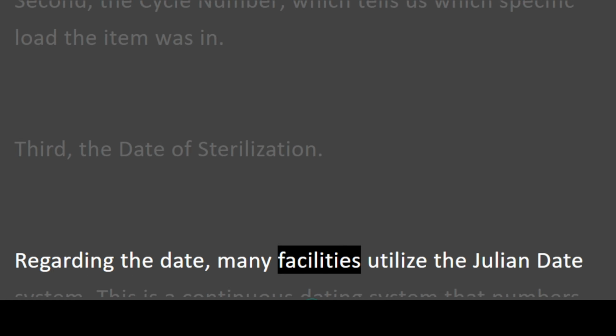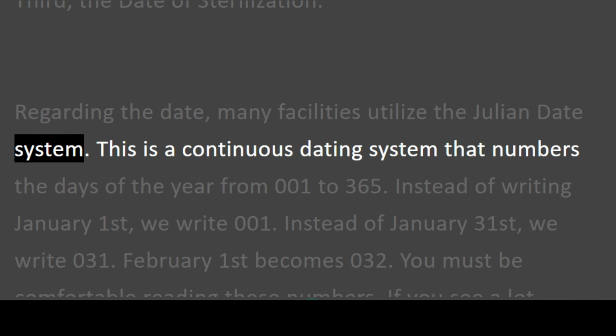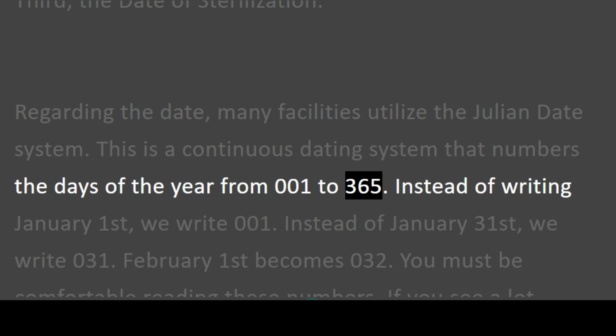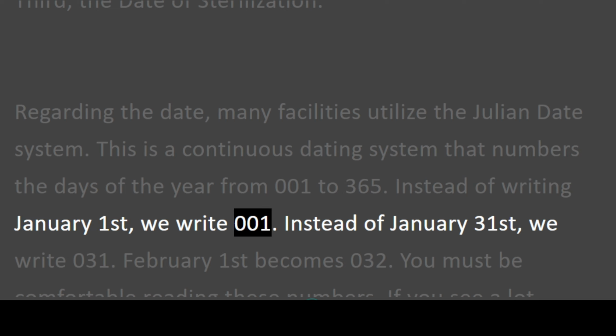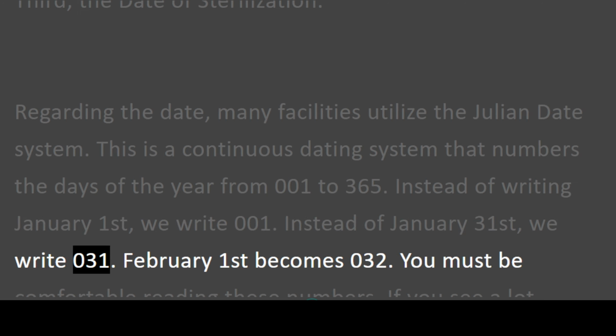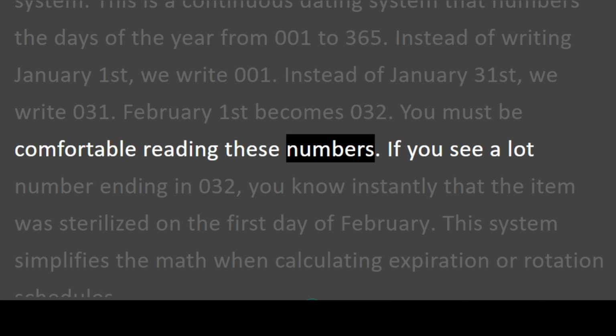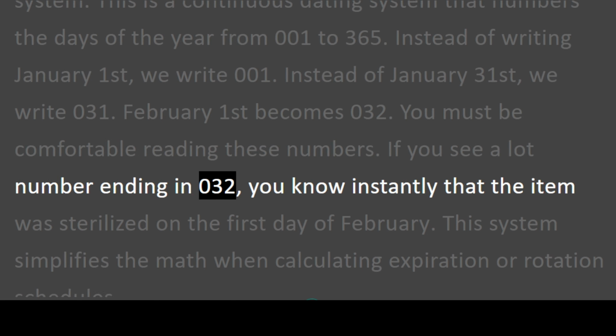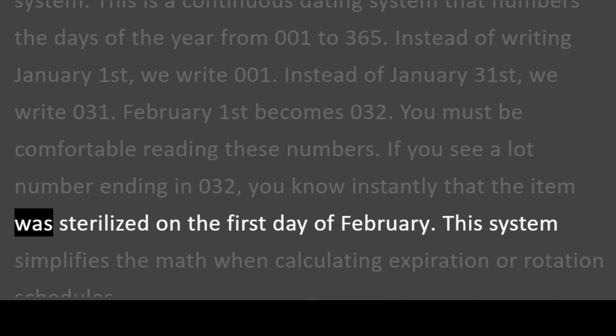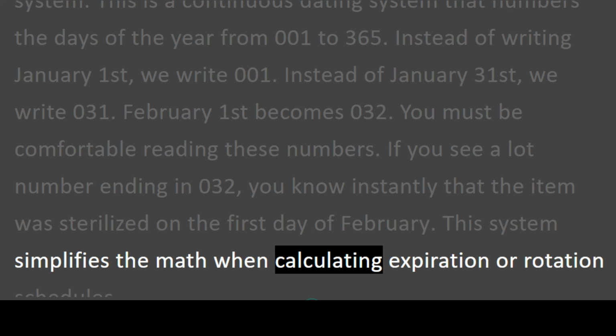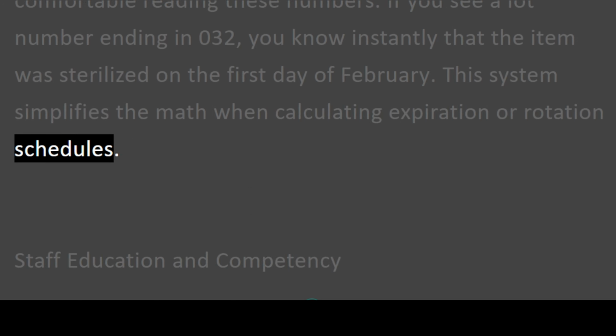Regarding the date, many facilities utilize the Julian date system. This is a continuous dating system that numbers the days of the year from 001 to 365. Instead of writing January 1st, we write 001. Instead of January 31st, we write 031. February 1st becomes 032. You must be comfortable reading these numbers. If you see a lot number ending in 032, you know instantly that the item was sterilized on the first day of February. This system simplifies the math when calculating expiration or rotation schedules.